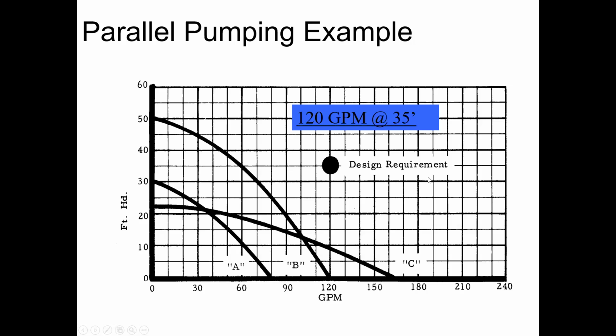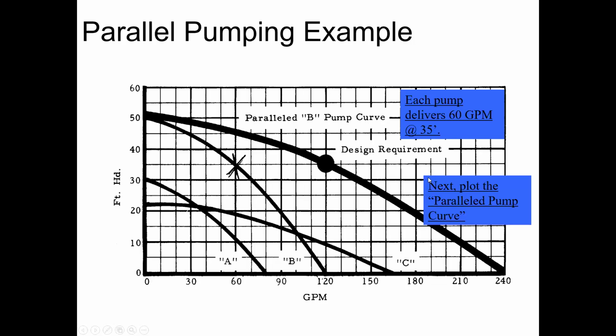I say, okay, I'm looking for 120 at 35 feet of head. Half of 120 is 60. Oddly enough, I have a curve, pump B we'll call it, that can deliver 60 gallons a minute and overcome 35 feet of head. So I'll pick 2 of those. So I'll build a parallel curve. So all I'm doing is taking that 60 and doubling it.